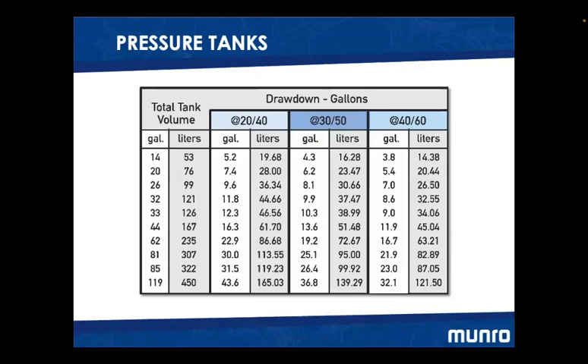In short, when utilizing pressure tanks and applying them properly, it may take multiple pressure tanks on a pump station in order to control the short cycling to a manner that is acceptable. Alternatively, we can use variable frequency drives. With those, we can do some controls that allow us to not use pressure tanks. So by not using the pressure tank and applying a variable frequency drive, we can control the short cycling much easier than if we didn't have a variable frequency drive and were just applying a pressure tank to it. Pressure tanks can be useful, but in large irrigation systems, most of the time, we have enough storage of air in the irrigation system that we can control the short cycling very easily with just the variable frequency drive.